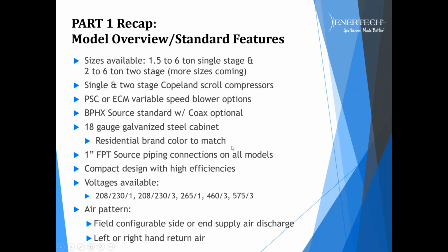It's what Enertech has been known for. When we design products, we're really trying to fit both the retrofit market and the new construction market with one product versus multiple tiers. Our goal is always to design a very small cabinet, but with high efficiency, to make sure we meet the Energy Star standards and the ASHRAE 90.1 standards, which this product more than meets. We have all the voltages available, both residentially and commercially. The air pattern is field convertible from side to end discharge, and the right and left-hand return air would be ordered as such.